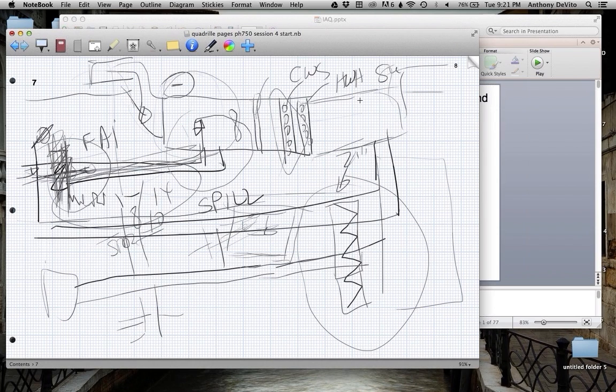Wintertime, same deal—you can't get it warm enough, people complain it's too cold. The other reason they might open or close this damper is that the building manager, maybe costs are a problem. What happens in the wintertime when you pull in cold air and you have to heat it? It costs money. Even worse in the summertime, you pull in hot air and you have to cool it—costs even more money. So you significantly impact your cost depending on the percentage of outside air you pull in.